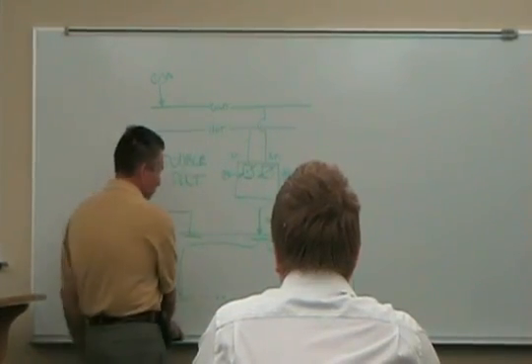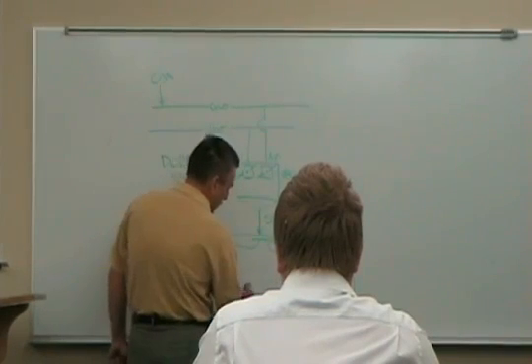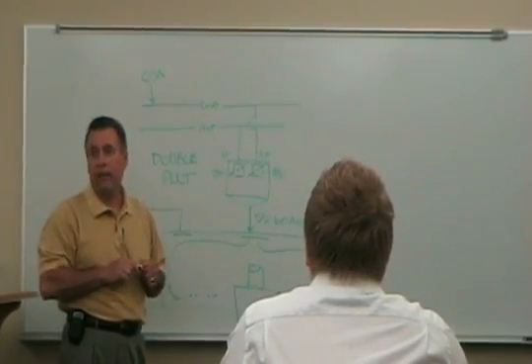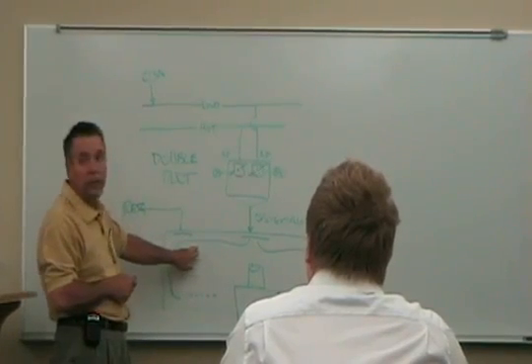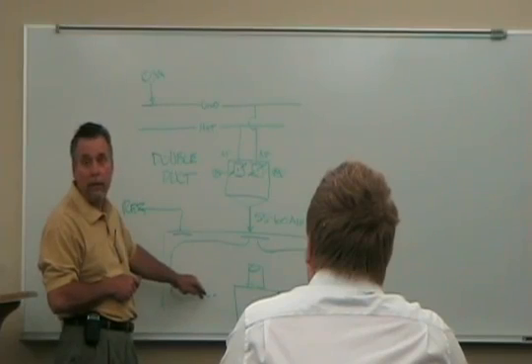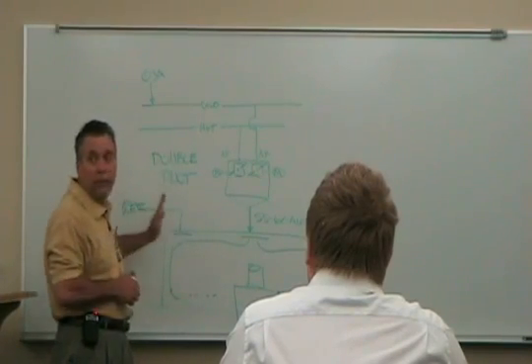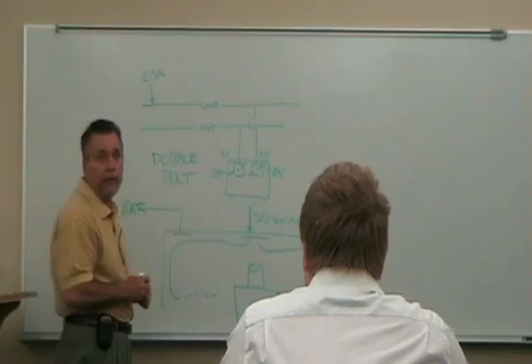The reason for that is in the summertime, this is 55 to 60 degree air. If my desk is right here, and I'm sitting at that desk, I don't want that air dumping on me. It creates a draft. So a proper diffuser, and these right here, in my opinion, are the only proper diffusers for a variable volume application. Send that air along the ceiling, it gets mixed with the room air, so by the time it starts going down the wall, it's close to room air temperature. But I'm still moving that much airflow through the space and then back out to the return, so I'm meeting my demand. That's the intent of the diffuser, is to mix with the airflow in the space so that you don't feel drafts.